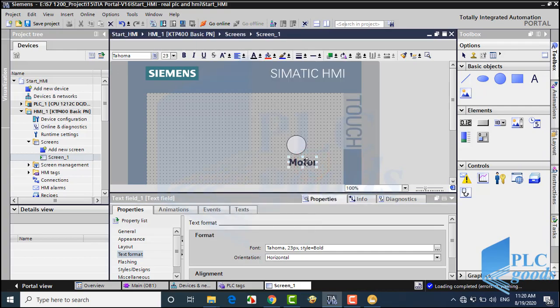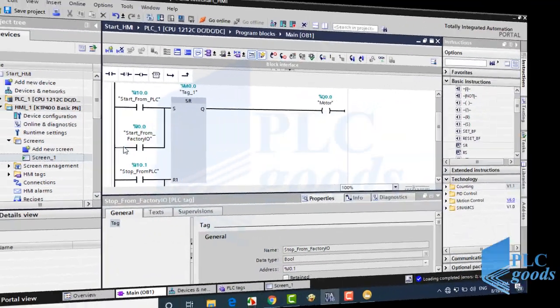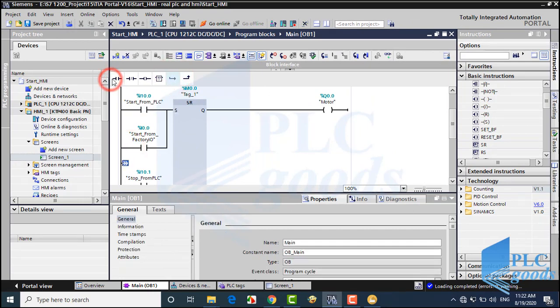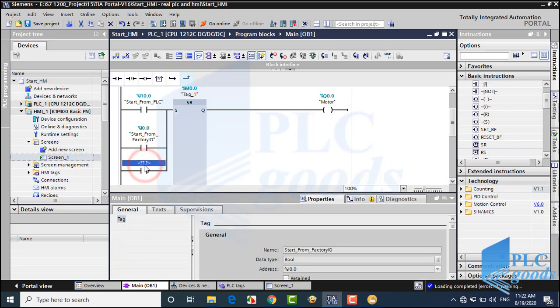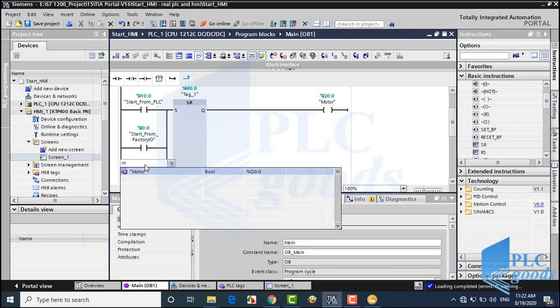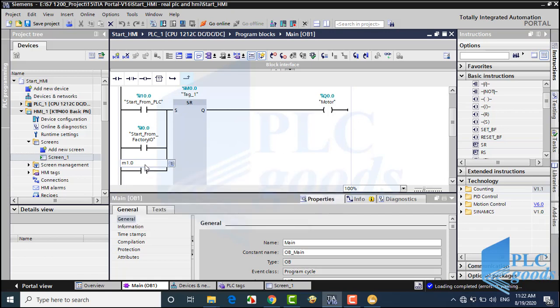How can we turn on and off the output from the HMI? Pay attention — the HMI can't change the PLC inputs, but it can modify PLC memory. So I can use two contacts with a bit of memory address, which can be changed by the HMI.